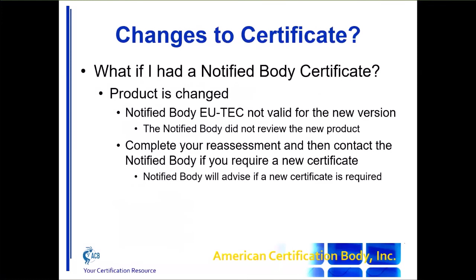What if I did have a notified body certificate and I change my product? Well, then the notified body certificate becomes invalid because you've made a change and haven't told the notified body about it. So contact the notified body and figure out between you if you need an update to the certificate or not. Similarly, if the standard has changed, the notified body certificate doesn't cover that new standard, because the notified body didn't review the product against it.